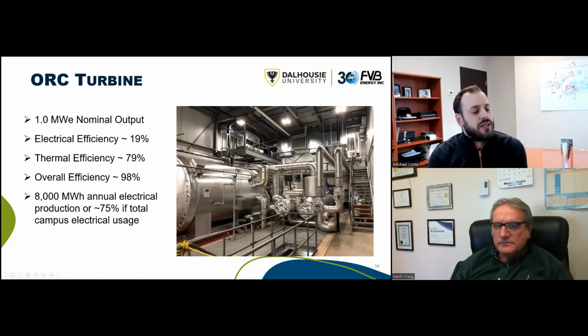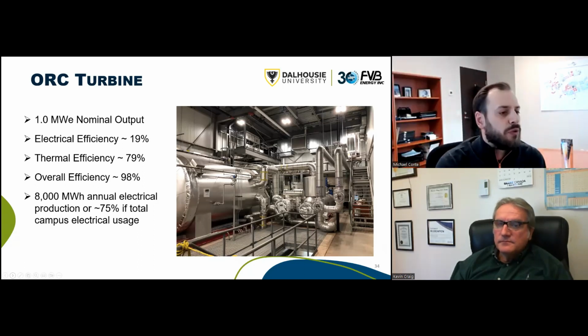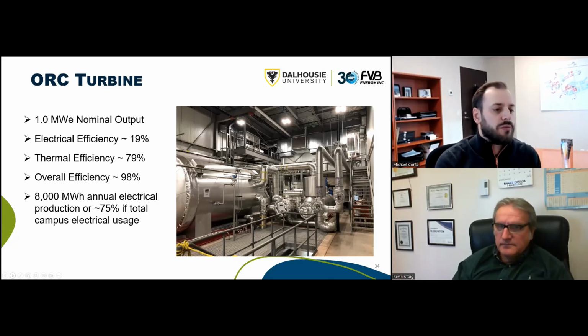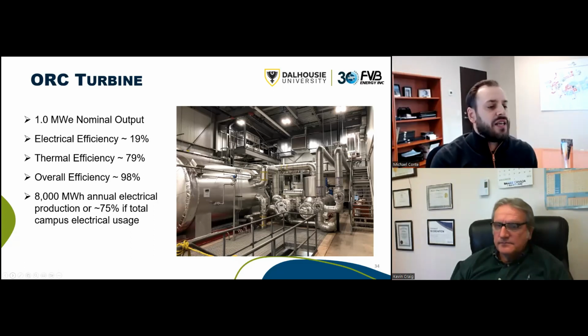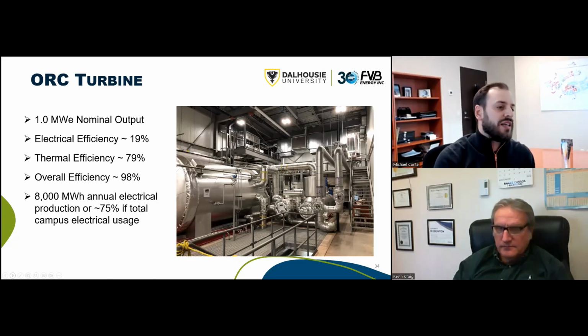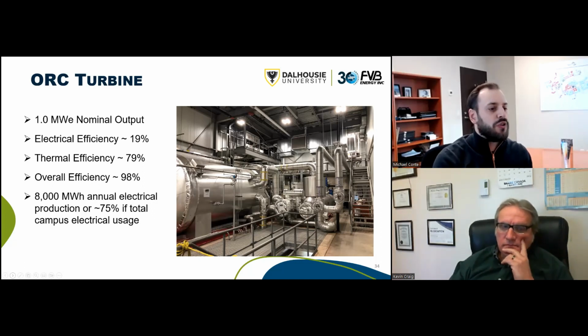So the biomass heater uses a thermal oil heater. As the biomass is combusted, it heats up a closed loop thermal oil system to a high temperature, and that oil is circulated to our organic Rankine cycle turbine. The turbine takes the high temperature oil and converts it into electricity via the organic Rankine cycle process and the connected generator. The cooling from the turbine is rejected as heat into our district heating system. Combining electrical and thermal efficiencies, it's a very high efficiency unit, with 98% of the energy recovered as either electricity or useful thermal energy.